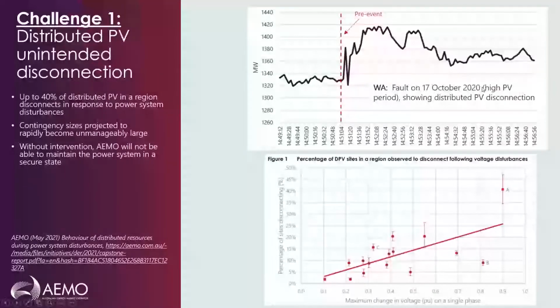Normally what we see with a fault is that load will trip off in a severe fault, and we'll see operational demand drop down after that event. But we're now seeing, for high PV periods, load will jump up a decent amount. We've seen this consistently across a bunch of events. Load will jump up because of PV disconnecting. It's more than offsetting the amount of load that is disconnected.